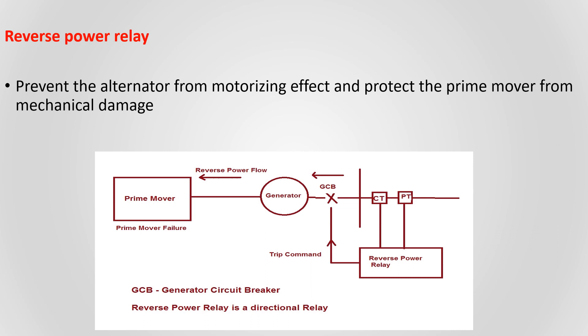When two or more generators are running in parallel, if there is a failure from any one of the generators, reverse power can flow from MSB to the alternator, and then the alternator acts as a motor. Because the ACB breaker is still in the closed position, the alternator starts to produce a magnetic field, and due to this magnetic field the rotor rotates and also rotates the prime mover. So in order to protect the prime mover from mechanical damage and to prevent the alternator from the motorizing effect, we are using a reverse power relay.